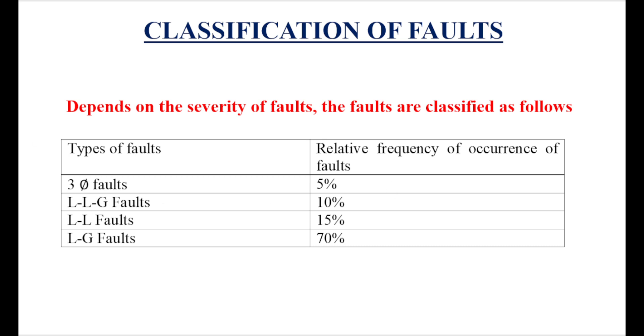Regarding frequency of occurrence: three-phase balanced fault occurs 5% of the time, LLG fault occurs 10%, LL fault occurs 15%, and LG fault occurs 70%. So LG fault has the maximum percentage of occurrence.